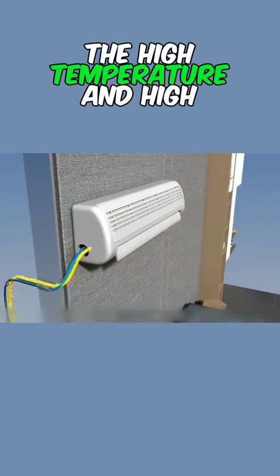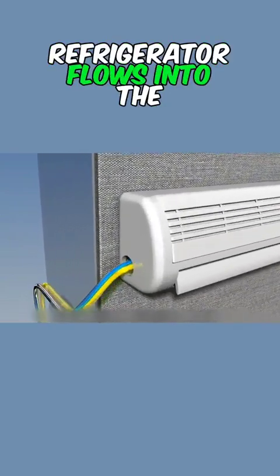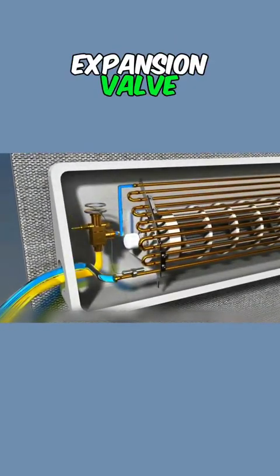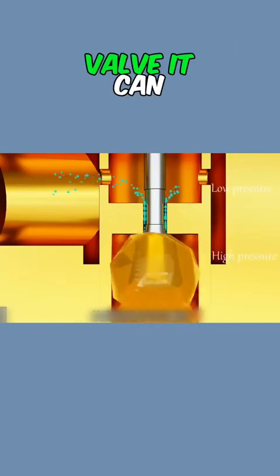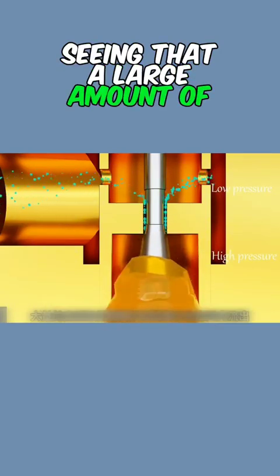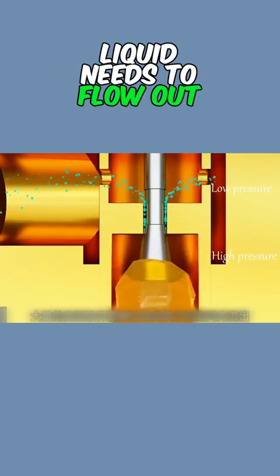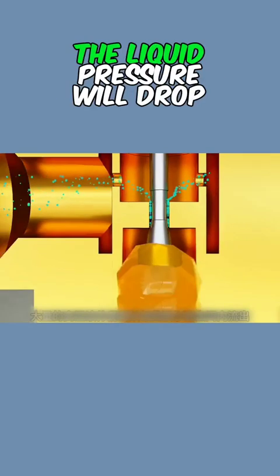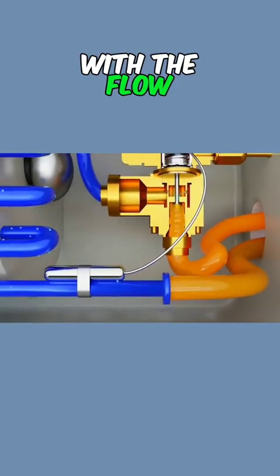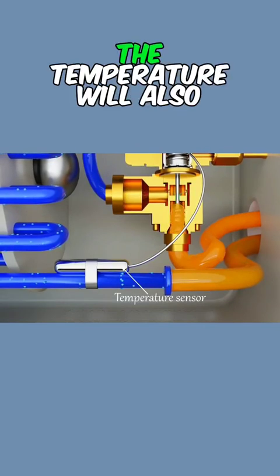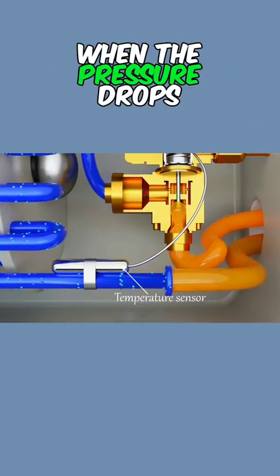The high temperature and high pressure liquid refrigerant flows into the expansion valve. Inside the expansion valve, you can see that a large amount of high temperature liquid needs to flow out from such a small space. The liquid pressure will drop with the flow. As mentioned earlier, the temperature will also drop when the pressure drops.